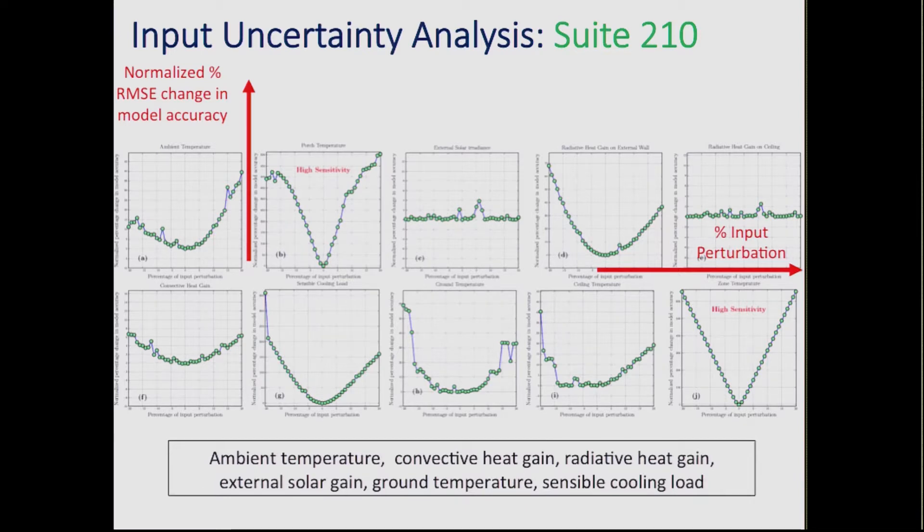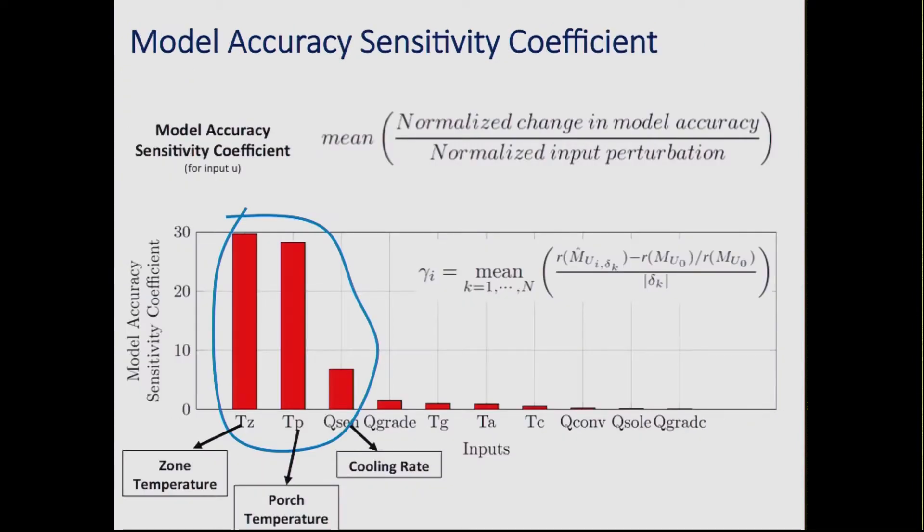But the second is that the decrease in accuracy is not same for all the different inputs. Some inputs are affecting the accuracy the most compared to other inputs. And that's really what we were trying to capture. So it would be very nice if we can get all this information and come up with a single number, which can rank these inputs in terms of how much they affect accuracy of the model. And that's what is called a model accuracy sensitivity coefficient. It's just a simple ratio of what's the average change in the accuracy to that of the magnitude of the perturbation that you added. So for this particular zone, it turns out, although you can measure 10 different things in your model structure, really, these top three things will affect the accuracy the most. So you should focus on adding sensors to get accurate measurements of these different inputs, as opposed to maybe the convective heat gain or some radiative heat gain.